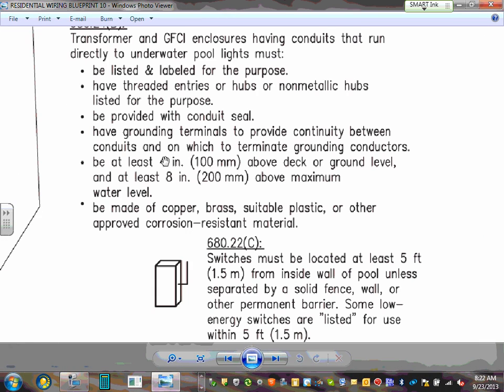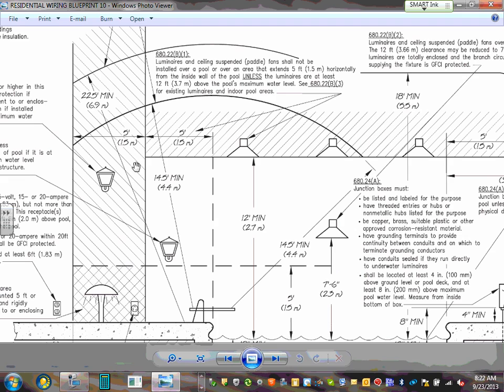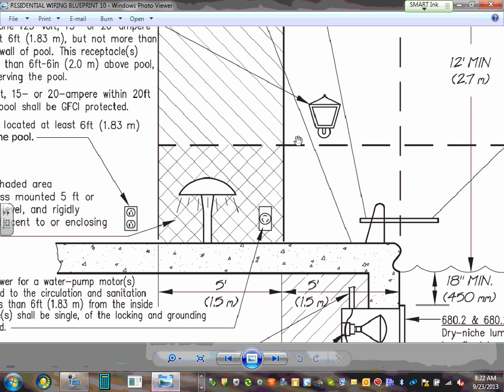All right, grounding. That's all I have, guys, for you in terms of the swimming pool. Any comments, any questions? Please feel free to review these. Like I said, for our project, don't forget that GFCI receptacle not closer than 6 feet that you need. Your pump is going to be on a GFCI circuit breaker, and your heater, we have a patio, so it's going to be under the patio, not above it, so it doesn't have to be affected.